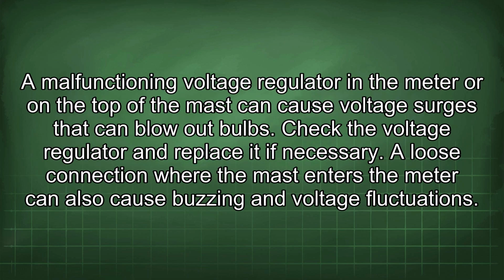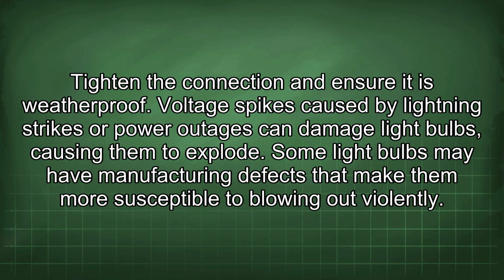A malfunctioning voltage regulator in the meter or on the top of the mast can cause voltage surges that can blow out bulbs. Check the voltage regulator and replace it if necessary. A loose connection where the mast enters the meter can also cause buzzing and voltage fluctuations. Tighten the connection and ensure it is weatherproof.